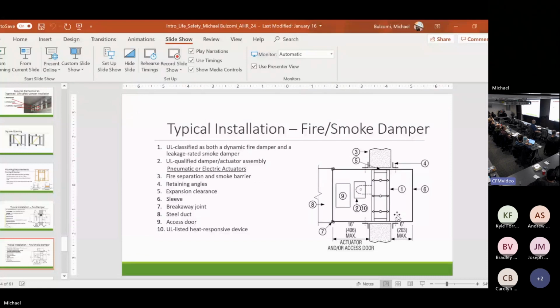Maximum, the sleeve can extend out of the opening. If I provide the access door on a fire damper, 16 inches. On a combination fire smoke damper on the actuator side, 16 inches. On the non-actuator or non-access door side, 6 inches maximum. So let's say I have a 4 inch partition: 6 plus 4 plus 16, 26 inch sleeve maximum.